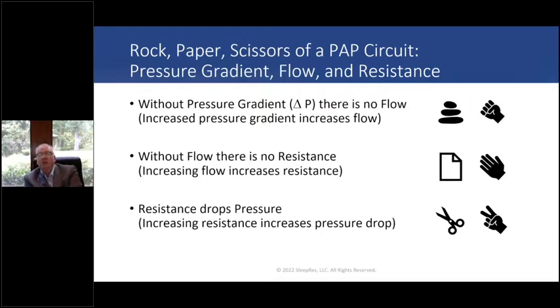Now I will say this, the third answer was a little tricky. It says drops both, I said directly drops both. If you have resistance, you can indirectly drop flow, because as you drop pressure, you drop the pressure gradient, which will drop the flow. But straight out, directly, resistance drops pressure. And that's so key to understanding the PAP circuit.